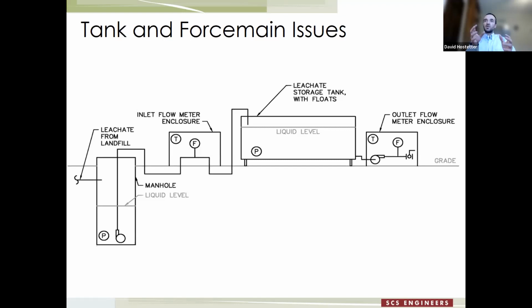Since there are those flow meter enclosures, we noticed there were times when the heaters in them would shut off - too much current was being pulled by the heaters, the breaker would trip, and the heater would just go off with no heat. So to be proactive instead of reactive with these problems, we installed thermocouples in both flow meter enclosures that tell us on a minute-by-minute basis what the temperatures are within those enclosures.